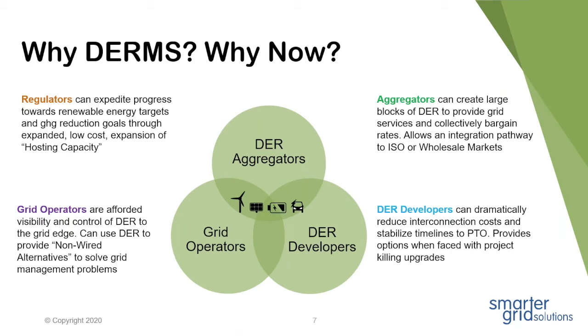What DERMS does is, as the system starts to approach this calculated breakdown point — which is very rare, maybe occurring 10 or 15 minutes over the course of a year — the DER takes action to prevent it from ever crossing that threshold, whether that's voltage, current, frequency, transformer capacity, islanding, or anything else.